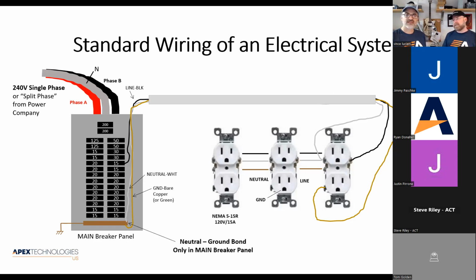And the other thing these dealers fight quite often is that they ask for the 20 amp circuit, which they got, but at the wall outlet is a NEMA 5-15R. Yeah, and that's pennies. You just get it swapped out. Yeah, put a 5-20R. But you have to ensure that the wire is the right gauge. In general, the National Electrical Code says if you have a 20 amp circuit, you're supposed to use 12 gauge wire. If it's a 15 amp circuit, you can go to 14 gauge wire. I like being very proactive and saying, in my equipment closet, I want dedicated 20 amp circuits, but I'd like you to use 10 gauge wire.